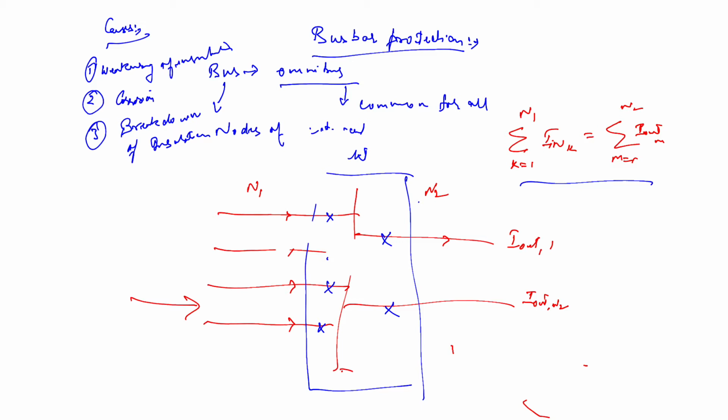It should be noted that the busbar fault lies in the overlap region between the two protective systems. Here we have one protective system, and here we have another, so the busbar falls within that. They do get backup protection, hence the protection engineers hesitated to provide exclusive busbar protection.